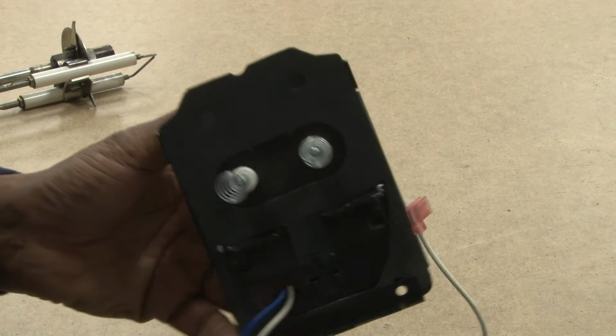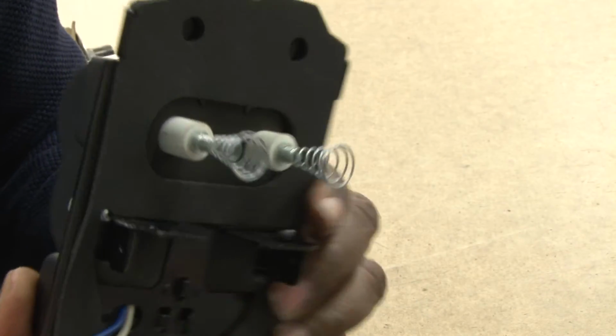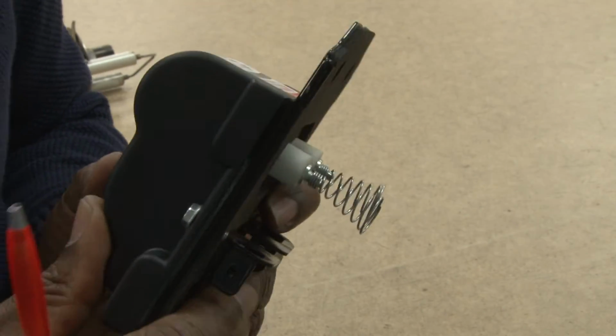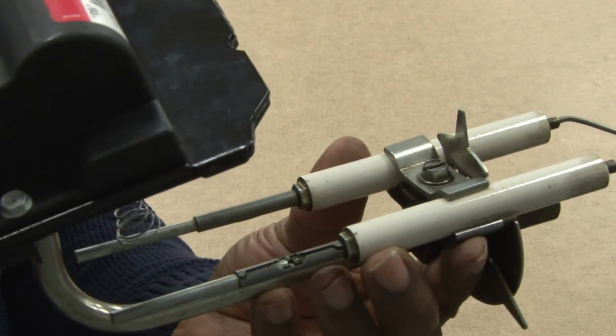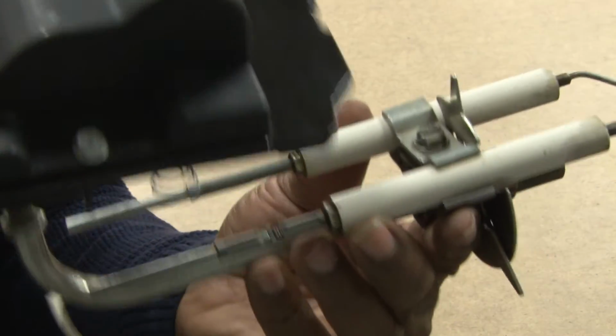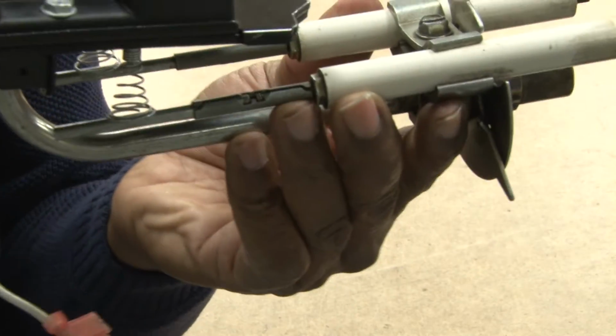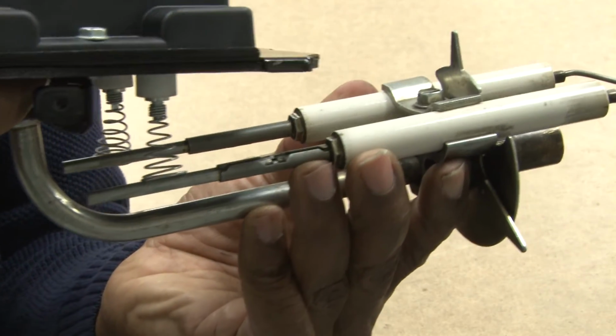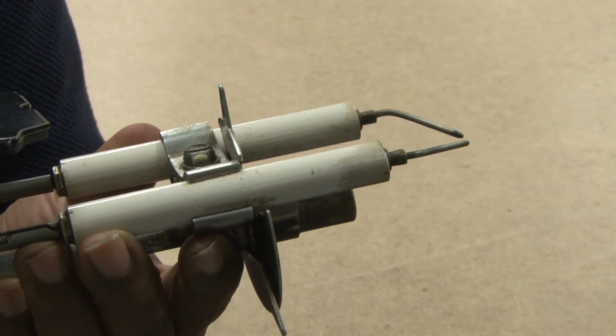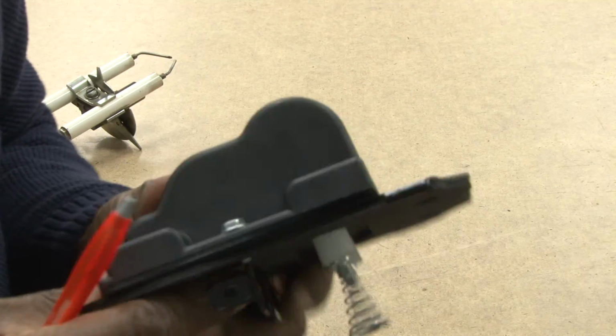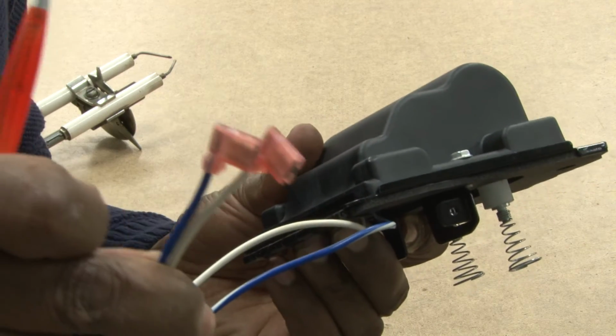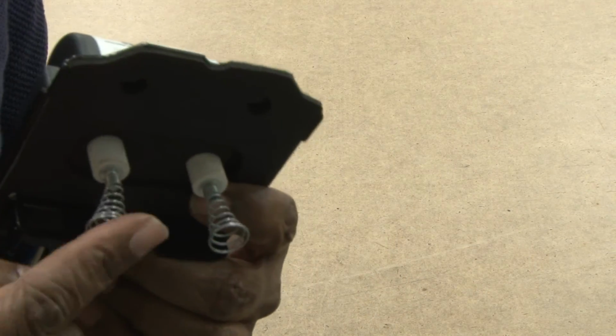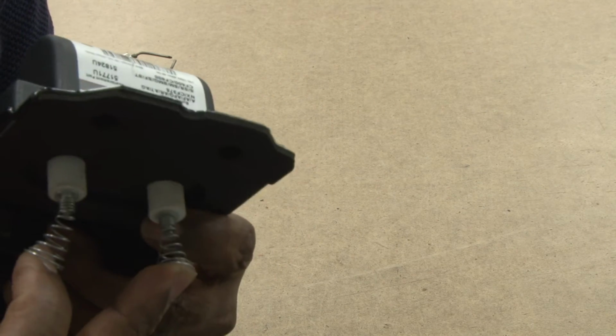Take a better look at a transformer. With this transformer, we can see where the electrodes are coming out, the springs, and like I said, it will rest on this device where you see the igniter. Basically the springs will rest on top of it, and it will cause it to spark at the end of the electrode. So the transformer takes 110 volts coming in, but it produces between 8 to 10,000 volts at these electrodes.